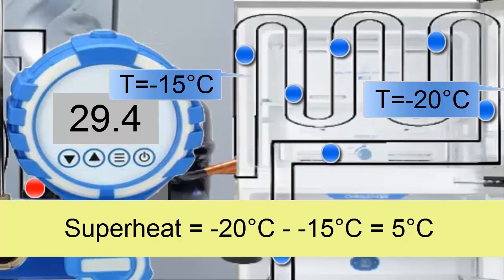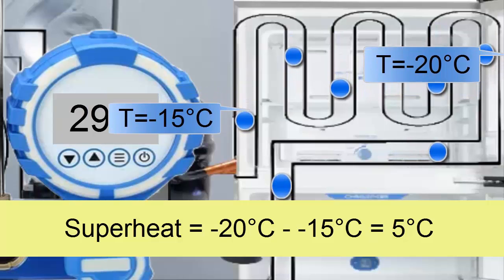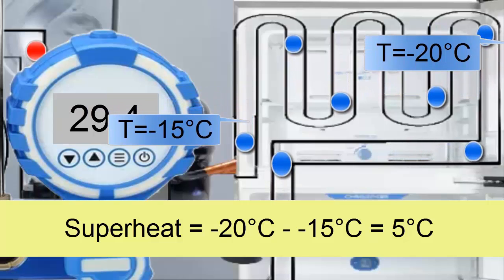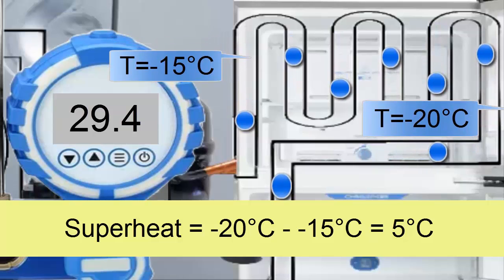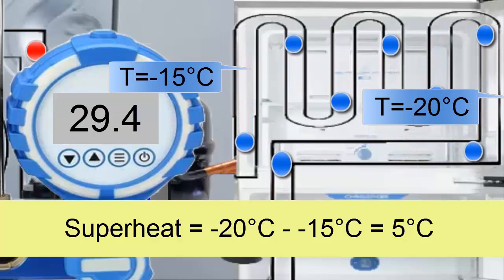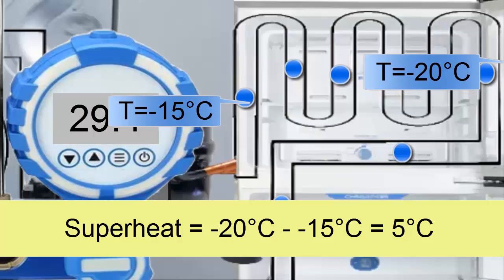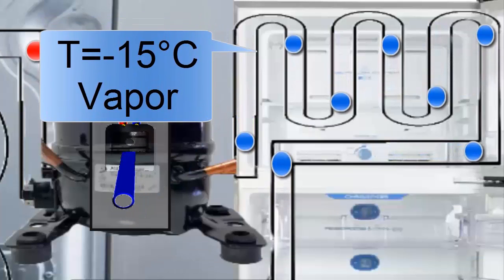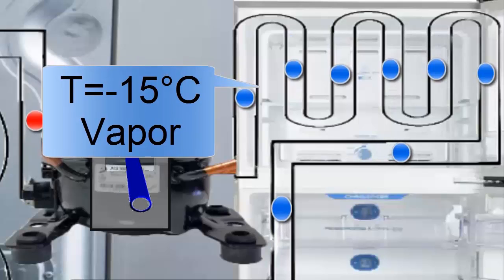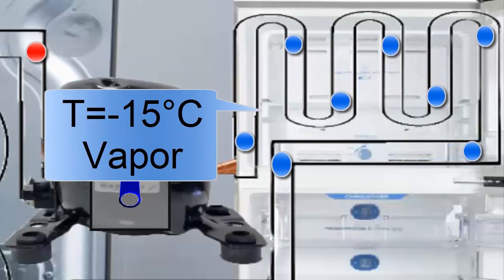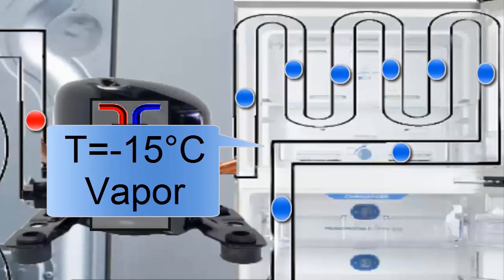Although the temperature has a slight change, we can approximate and say that the pressure of the R404A at the evaporator outlet is practically the same, still 29.4 pounds per square inch. The R404A, now in a vapor state, heads to the compressor through the suction pipe, which we can identify as the thickest pipe of the compressor.